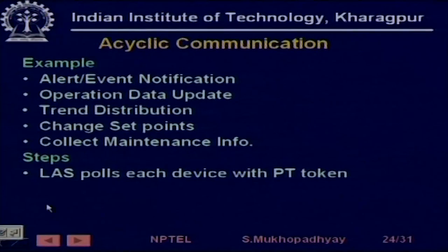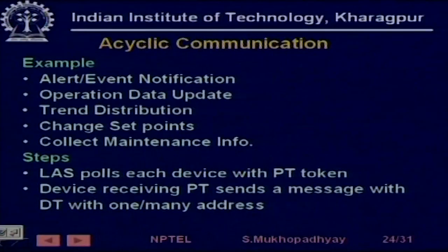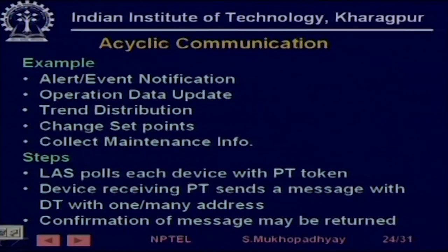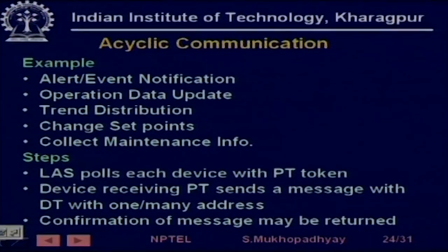For this, the LAS polls each device with a PT token. PT is a pass token. If a device has something to communicate, it will take the pass token and then communicate. If it doesn't have anything to communicate, it will simply pass the token to the next device. So whoever needs it will hold the token and then transmit the data.